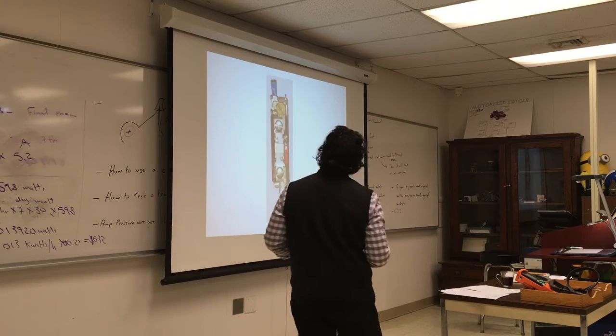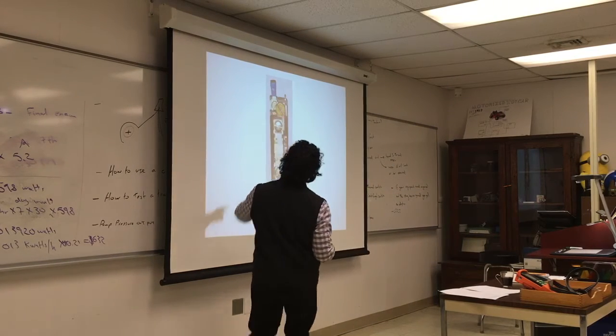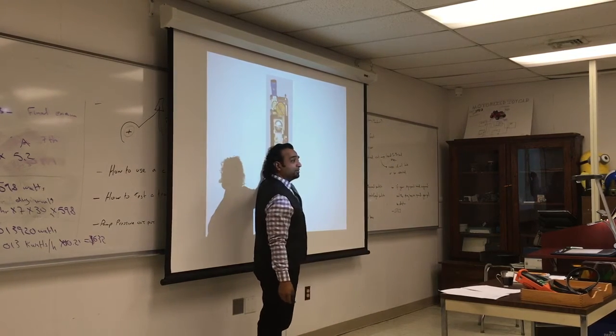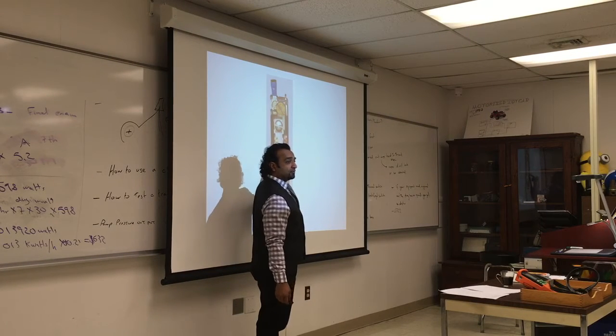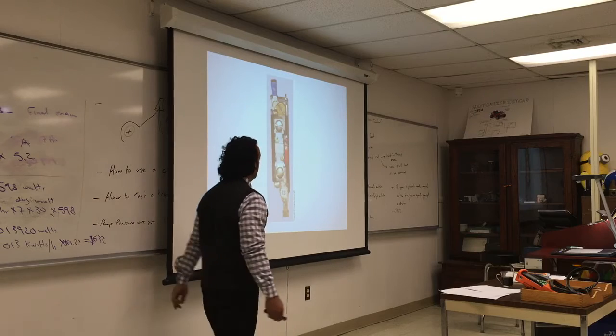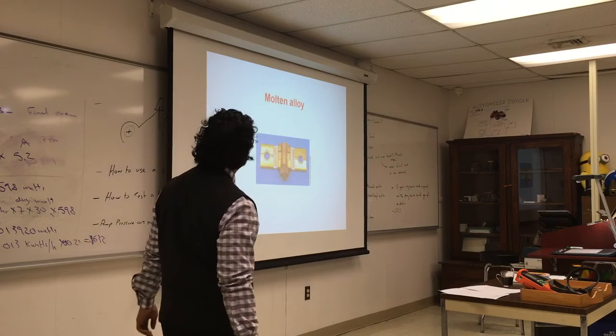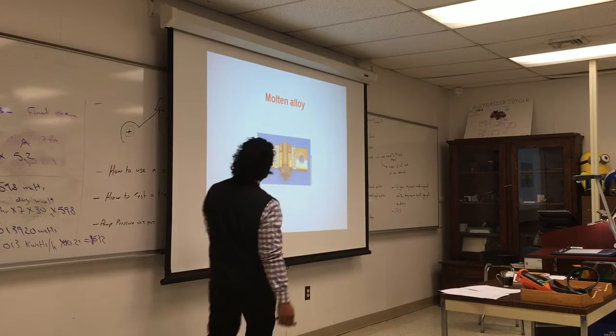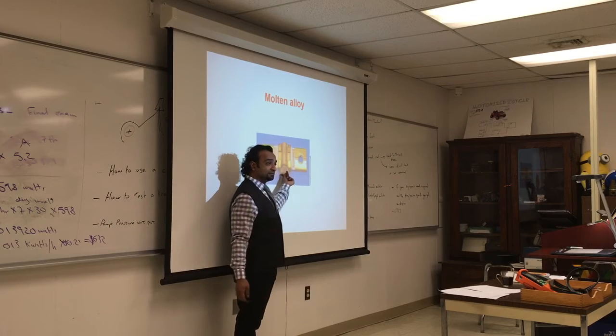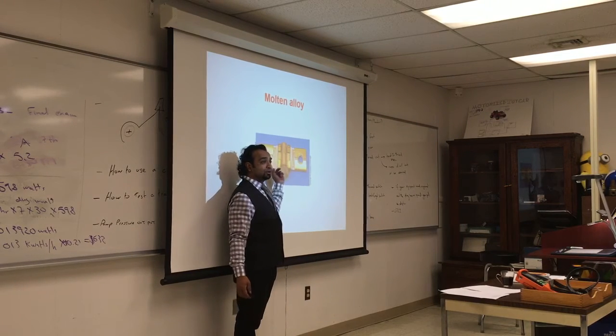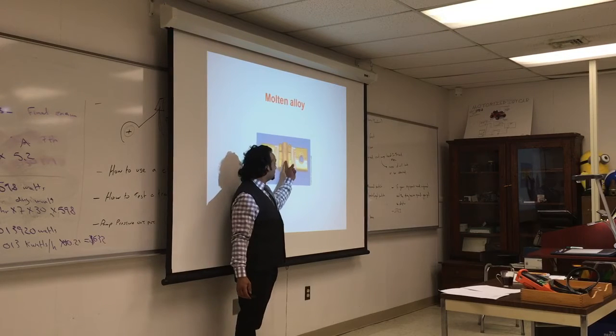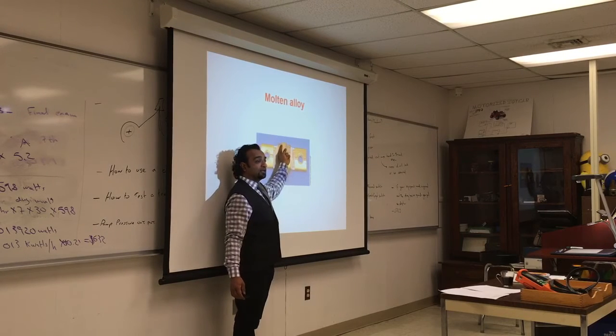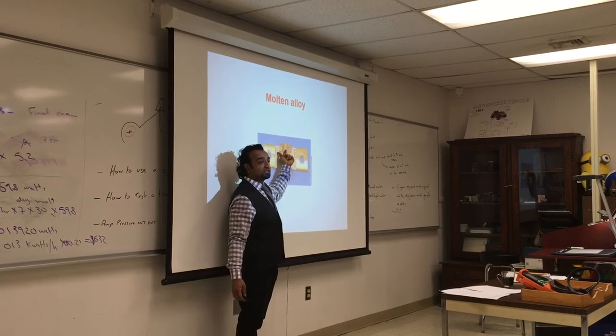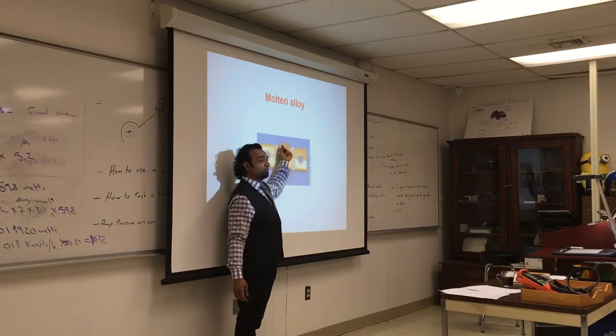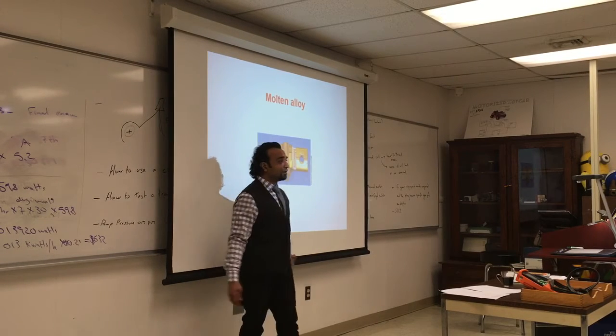That's what it looks like. Again, those are two contacts, and this is my molten alloy in the middle. It's not like using a wire. This will take a lot of heat, it will melt, and it will shut off the circuit. This one is gravity operated. There's a weight between the two terminals, and it's filled with lead. Once it overheats, the lead melts at around 400 degrees, it gets soft, and the weight will drop down.